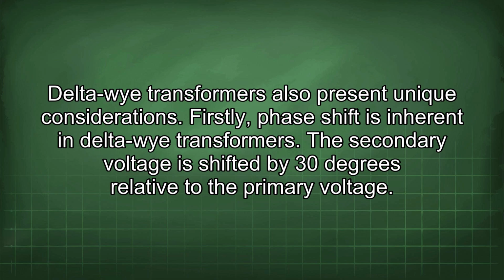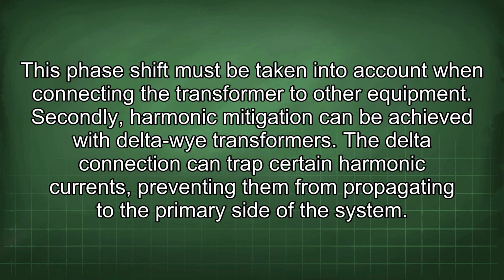Delta-wye transformers also present unique considerations. Firstly, phase shift is inherent in delta-wye transformers. The secondary voltage is shifted by 30 degrees relative to the primary voltage. This phase shift must be taken into account when connecting the transformer to other equipment. Secondly, harmonic mitigation can be achieved with delta-wye transformers. The delta connection can trap certain harmonic currents, preventing them from propagating to the primary side of the system.